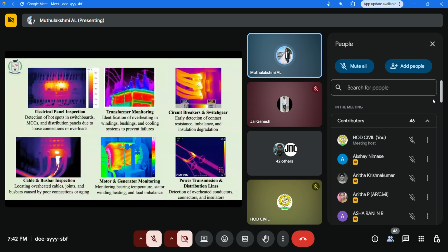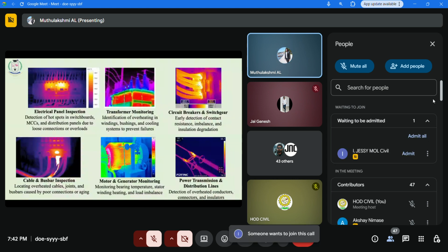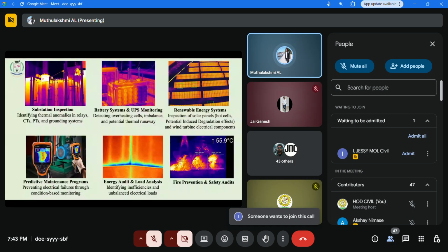And then motor and generator monitoring. Why do we take pictures of motors? In industrial settings, motors run at high temperatures, so we can't manually touch them or find defects without stopping production. Without stopping production, we have to find if there's any fault, defect, or maintenance need for the equipment. Through this camera we can analyze temperature differences between normal and abnormal.